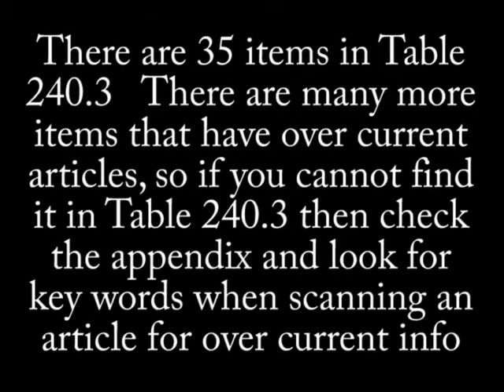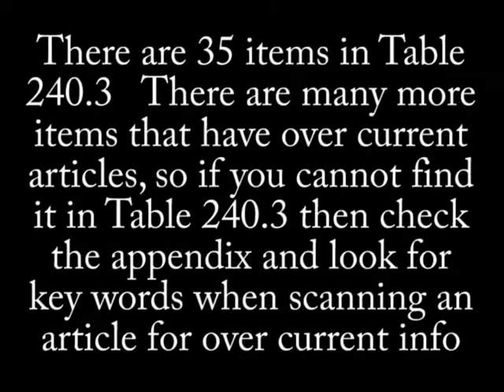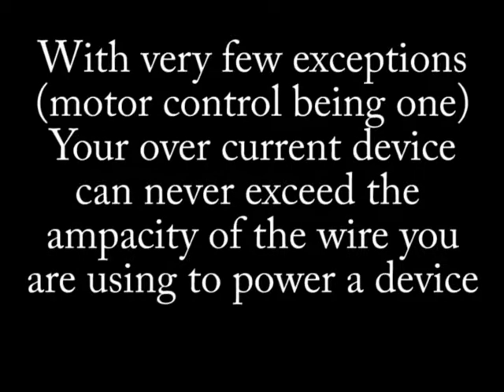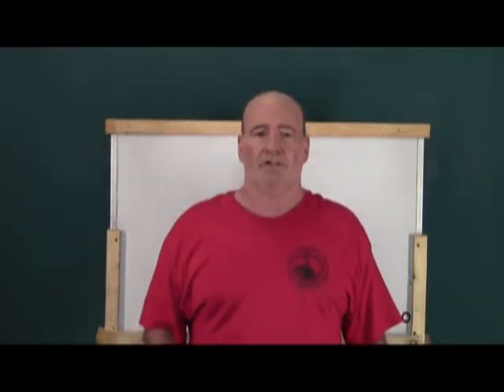Although there are 35 items in table 240.3, my main goal was to show you how to use it to track down overcurrent requirements for various situations. If asked an overcurrent question, you should first refer to table 240.3 and look for keywords like disconnect requirements or overcurrent requirements. If you cannot find your item in table 240.3, then look in the appendix for what article it comes under and begin your search there. With few exceptions, your overcurrent device can never exceed the ampacity of the wire being used on that circuit. That just about wraps up this episode. Thanks for watching and have a great day.